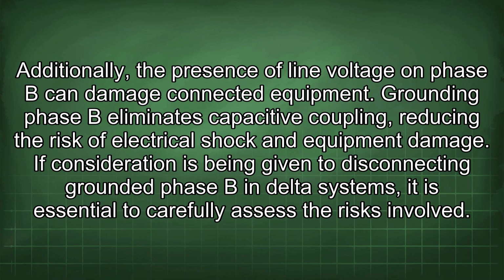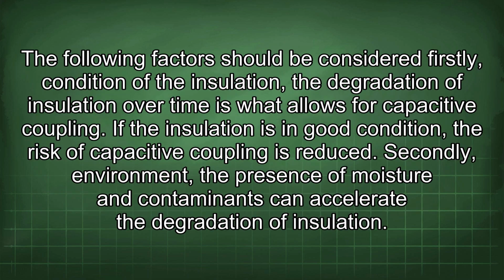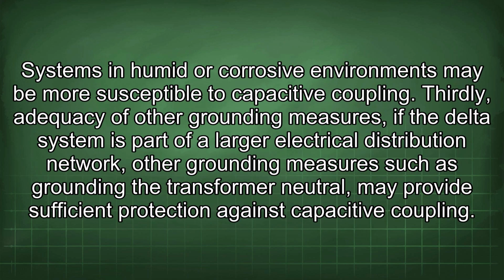If consideration is being given to disconnecting grounded phase B in delta systems, it is essential to carefully assess the risks involved. The following factors should be considered. Firstly, condition of the insulation. The degradation of insulation over time is what allows for capacitive coupling. If the insulation is in good condition, the risk of capacitive coupling is reduced. Secondly, environment. The presence of moisture and contaminants can accelerate the degradation of insulation. Systems in humid or corrosive environments may be more susceptible to capacitive coupling.